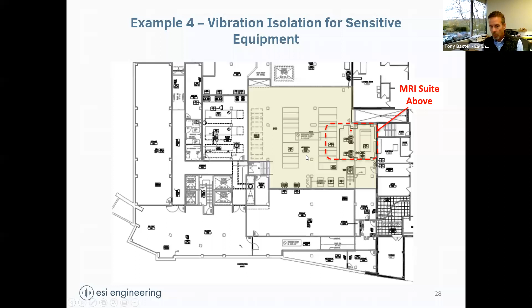So for this project, they griped about all the isolation that was going to have to be done. The mechanical engineer told me they spent $250,000 on isolation for the mechanical rooms. So we went back after it was built and made vibration measurements.